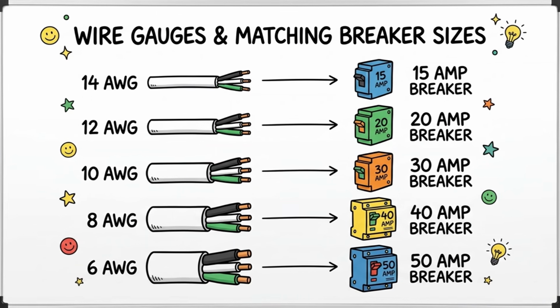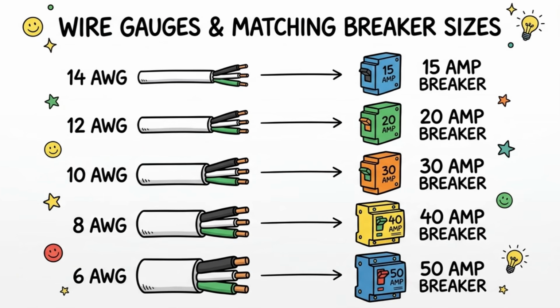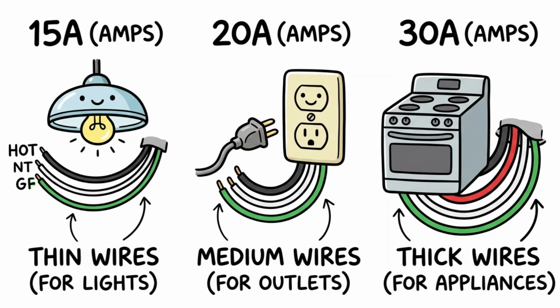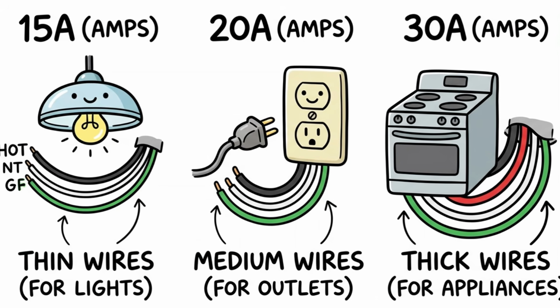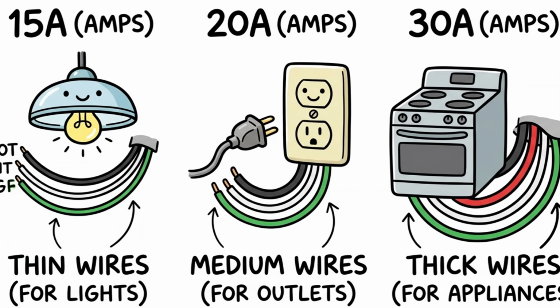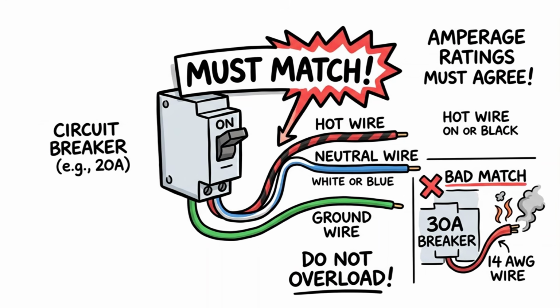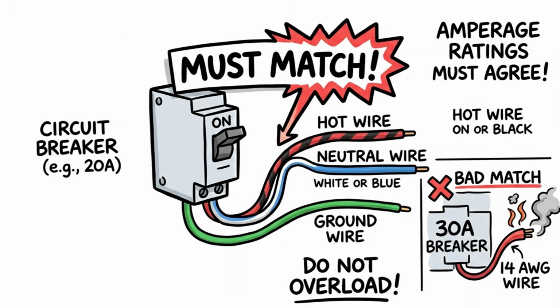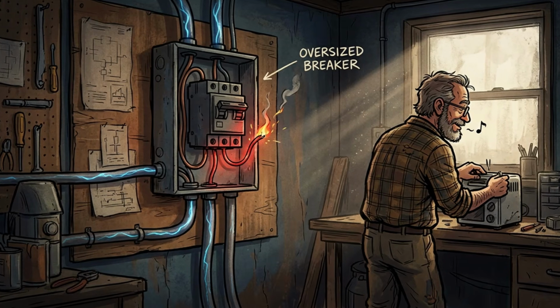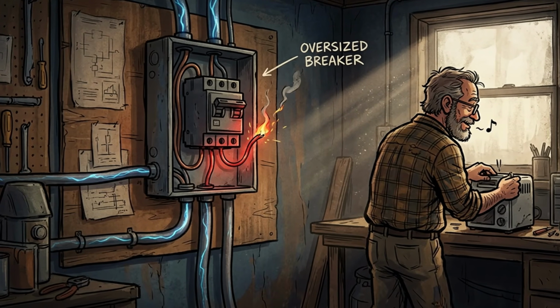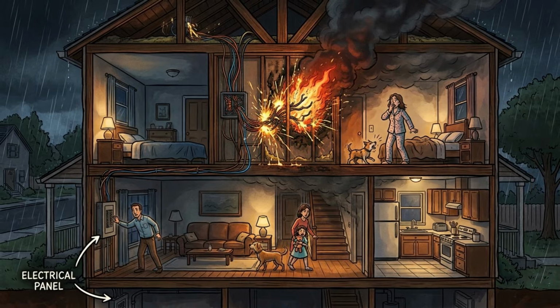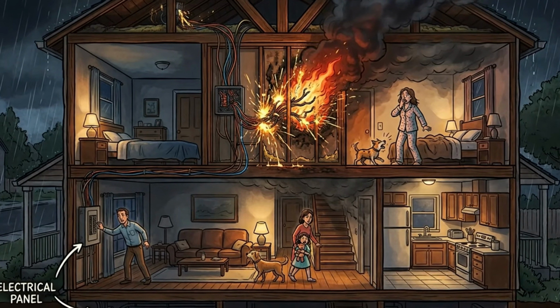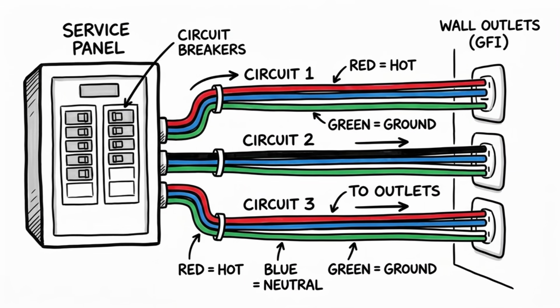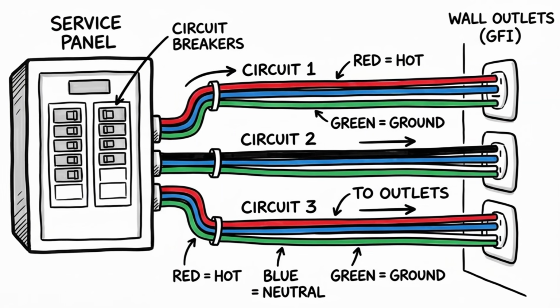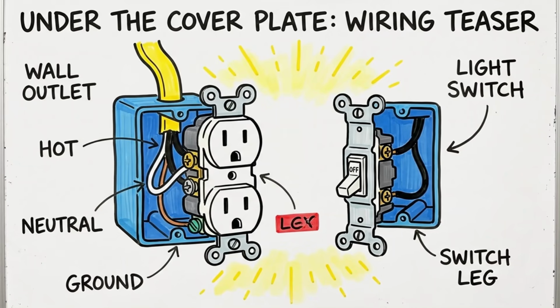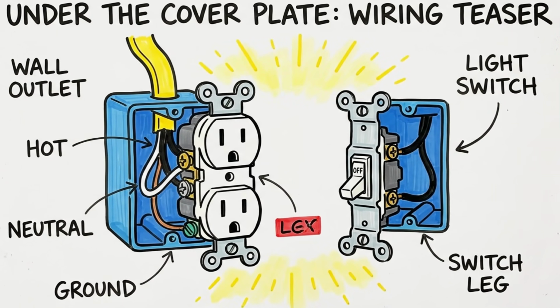And the thickness of the wire is carefully matched to the breaker protecting it. A small 15-amp breaker guards thinner wire for lights. A heavier 20-amp breaker protects thicker wire for outlets. And big appliances use even thicker wire still. This matching is absolutely critical, and getting it wrong is genuinely dangerous. Put a bigger breaker on a thin wire, and the wire can overheat and catch fire before the breaker ever notices. That single mistake is behind countless house fires. So every circuit leaves the panel perfectly matched, and heads to the places you actually plug in. Which brings us to the outlets and switches you touch every single day, and what's really happening inside them.